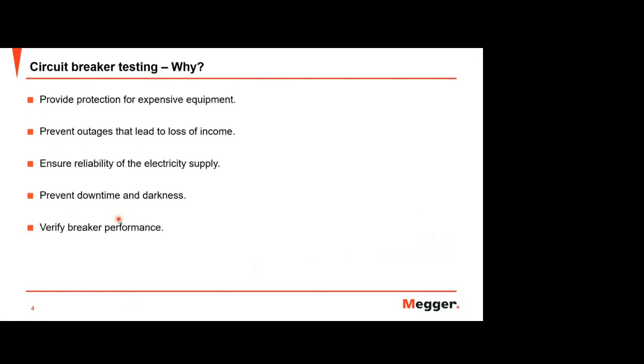Yeah, start from the circuit breaker testing. Why? Because first trip is part of the circuit breaker testing. So a key requirement from the electricity network is to provide safe, efficient, and reliable power to customers. So when a fault occurs due to maybe weather, equipment failure, or maybe accidental damage, then the circuit breaker must quickly disconnect the fault in order to protect the network upstream side of the circuit breaker and maintain supply to the majority of customers. So therefore, the circuit breaker can be considered as the guardian of the power network.